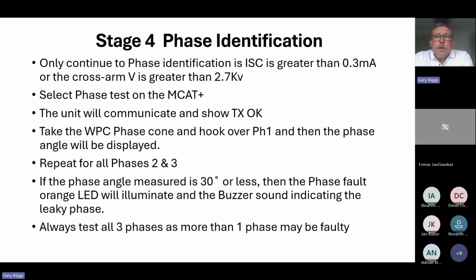On the test, we select phase test on the MCAT Plus. The unit will then communicate with a second probe, which we put up onto, first of all, phase 1. It will tell you yes, the two are communicating wirelessly and we're ready to carry on. So we take the cone, hook it over phase 1, and the phase 1 phase angle will be displayed in degrees. The unit will either say yes or no, that's the phase that's the problem. Because if the voltage and current sitting on that cross arm matches phase 1, that tells you the phase 1 insulator has broken down.